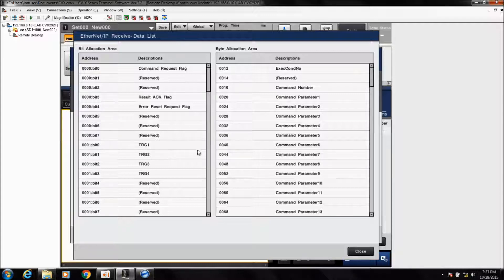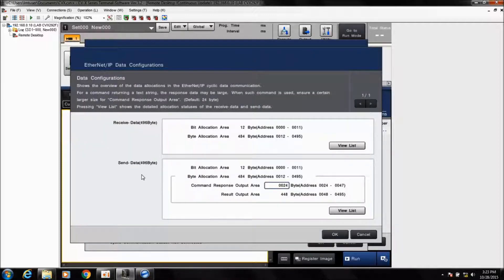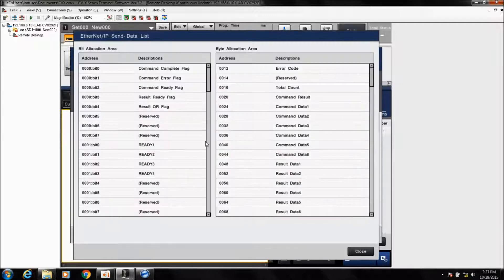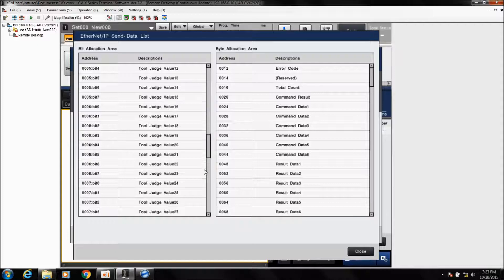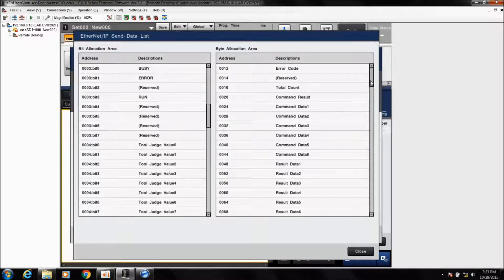On the input side you can see the CVX triggers and everything. On the output or send data side, the only thing that's really changeable is the command response output area — it's set for 24 bytes. Lowering that will give you more result output data, but normally you can leave this default. You can click View List to scroll through and see the different bits and byte areas allocated for Ethernet IP.